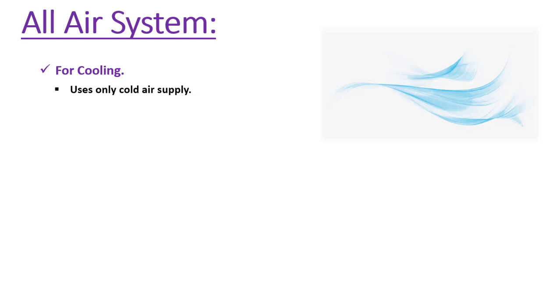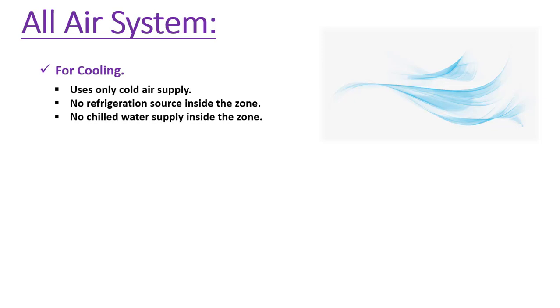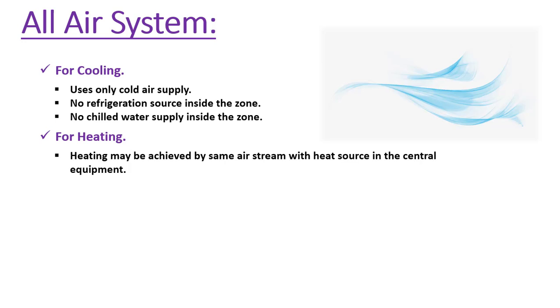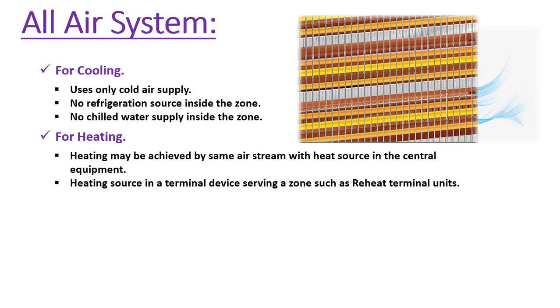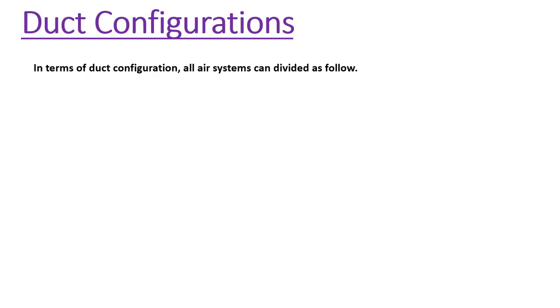All air systems provide cooling solely through cold supply air delivered to the conditioned space. These systems don't provide any supplementary cooling by refrigeration source within the zone or supply any chilled water to the zones. In all air systems, heating may be achieved by the same air stream with a heat source in the central equipment like an AHU, or heating can also be achieved by a heating source in a terminal device serving a zone, such as reheat terminal units.